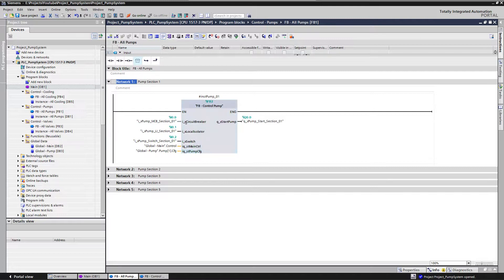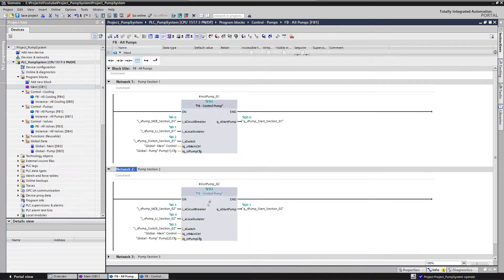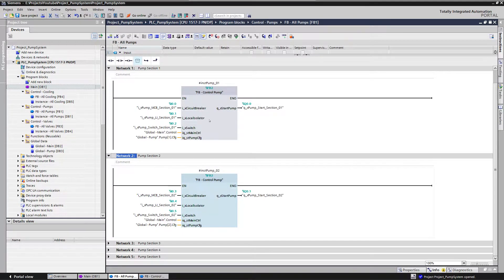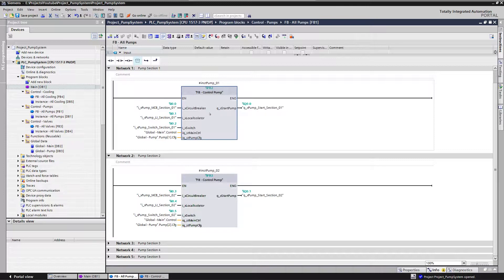In this 'control pump' function block I have all the necessary code to control one pump — for example a circuit breaker input, a local isolator input, a switch to turn the pump on or off, an output which starts the pump, and two structures connected to this function block: a main control and a pump configuration. I've copied this function block as many times as I have pumps — so five times — and the only thing different for each call are the inputs, outputs, and structures connected to the function block.